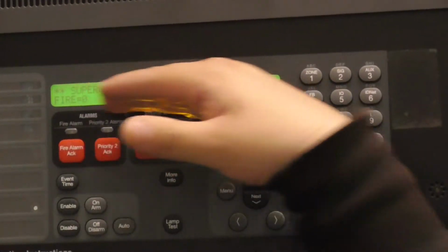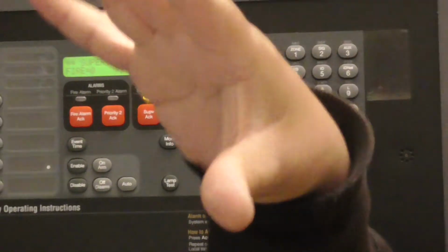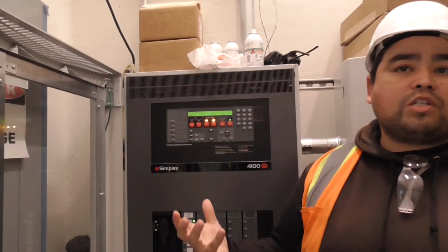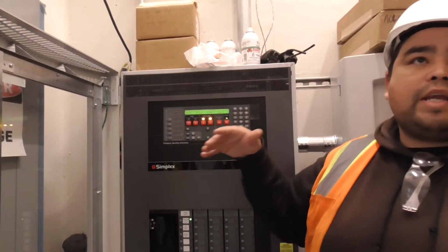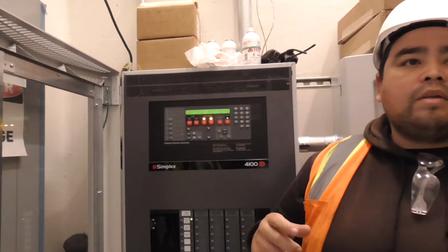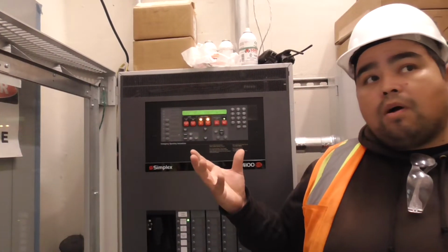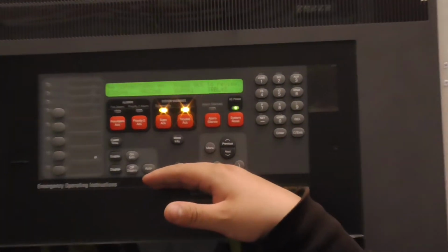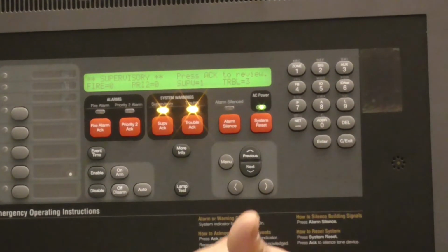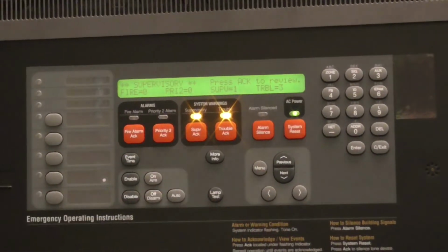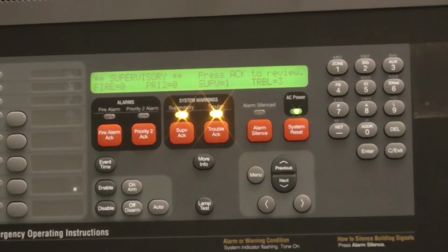So basically what you see here is going to be the exact same thing they see at PD, with the exception of if somebody takes down an addressable strobe. You'll get a general trouble here, and I'll tell you the strobe. Let's just say someone took down a strobe in building C, 6th floor, one of the apartments. They take down the strobe from the wall. It'll come in here as a no answer, the strobe. But PD won't see that specific description. They would have to come to the panel itself to get that. It's just going to tell them, hey, I got a common trouble at this building of housing. Got it. And it's not specific.